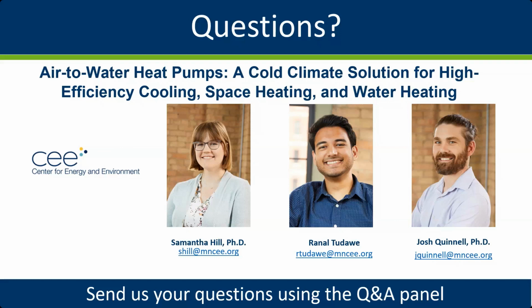Yeah, that also reminds me of another thing. If you could go on here, we actually saw some of this already when we started promoting condensing boilers a long time ago. They also deliver, for their optimum efficiency, supply temperatures that are considerably lower than these design temperatures. And so it's this sort of constant battle between the emitter capacity you can get out of your existing emitters and what you need for your building. And the challenge is actually a little bit separate from the heating plant, which can deliver sufficient capacity at those temperatures.